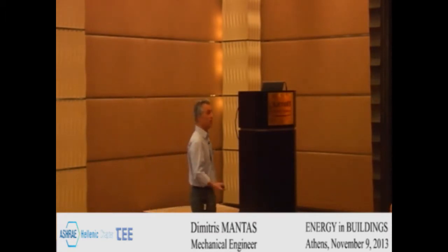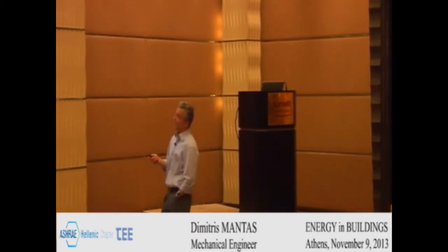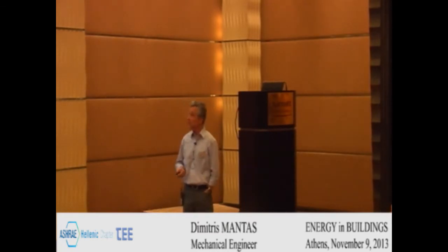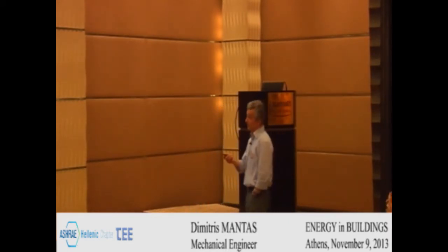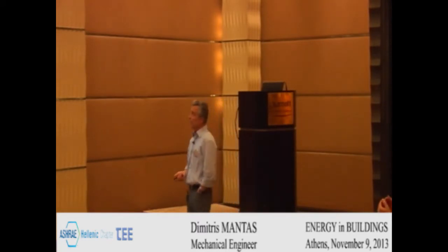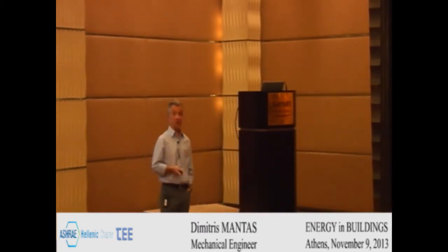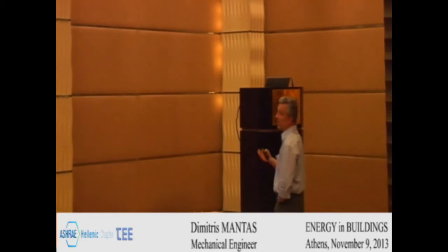Another set of data which we get from this open buildings library website gives us asset ratings and reality ratings, actual situation ratings. You see the differences between office buildings and all types of buildings, and we see the CIBSE ratings, which are quite close to the actual ratings. So we see that there is quite a big difference between estimates and reality, which is the main source for this difference. Looking into it, we should come to the three reasons.